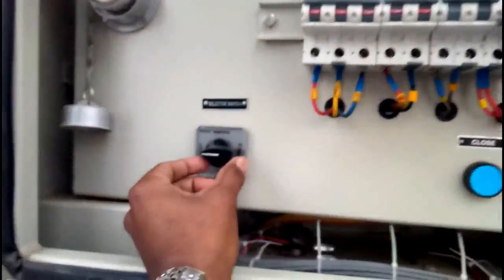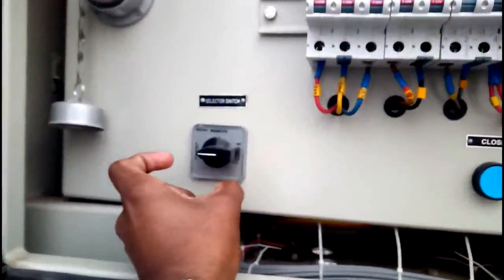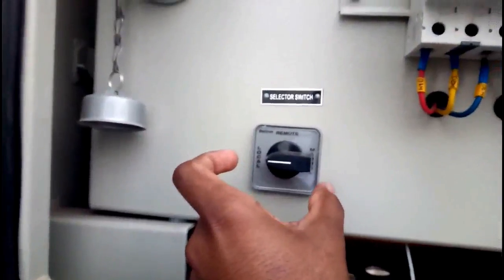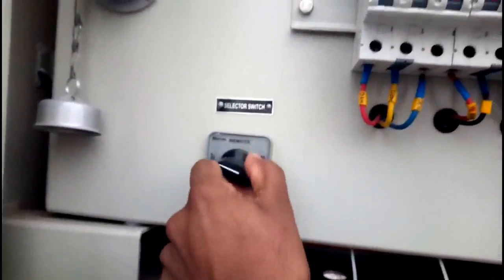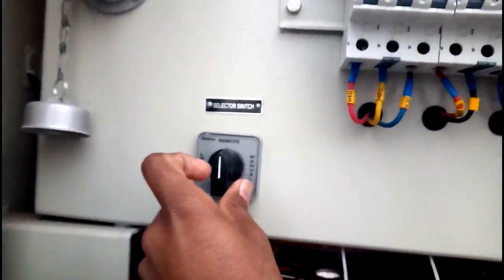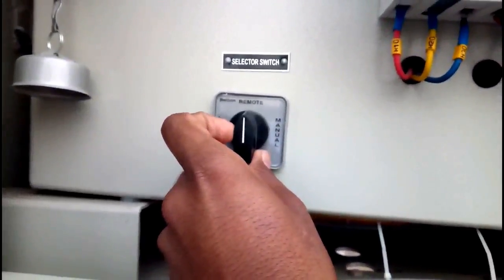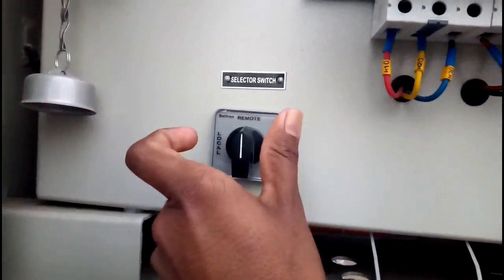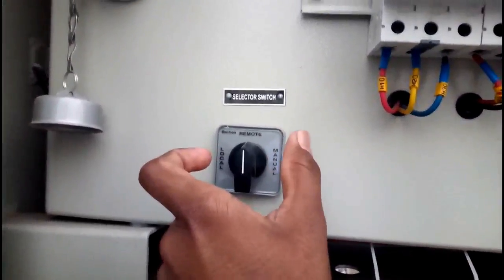I will also show you how we are operating. Here is the switch which should be in local mode, meaning we operate from here. When we change this switch to remote mode, we can control this isolator from the SCADA control room or from the relay panel, the BCU relay panel.